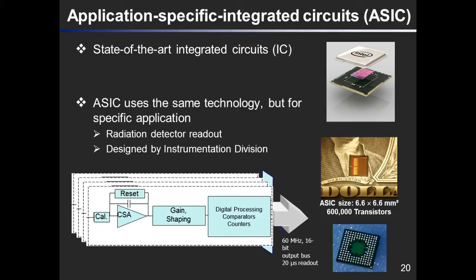In this chart, you see the signal processing for the detector pixels. We have the charge-sensitive amplifier to collect all the charge. Then we have the main amplifier to amplify the signal and also stretch out the pulse, make it longer, so we can measure the amplitude more precisely. Following that, we have the digital part to compare the amplitude of the signal to a threshold. If the signal goes over the threshold, we count it and increase the counter by 1. Basically, that's the photon counting application.